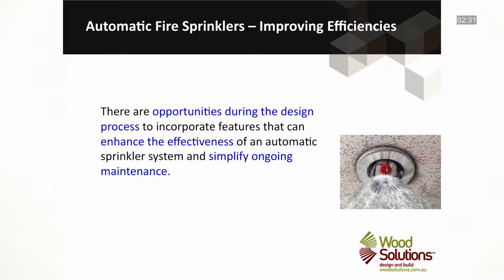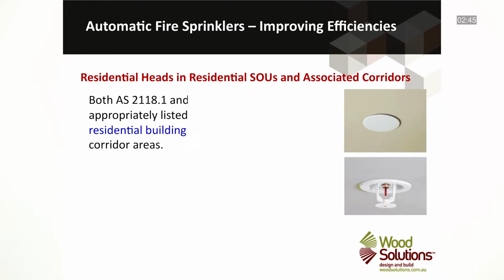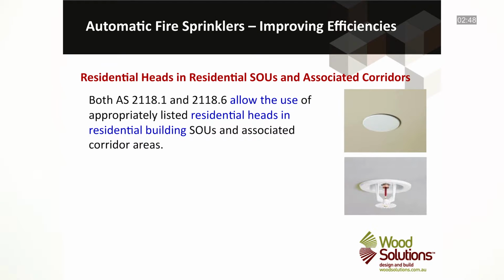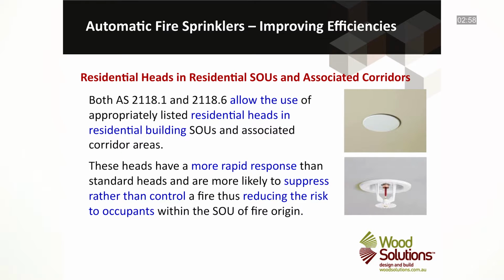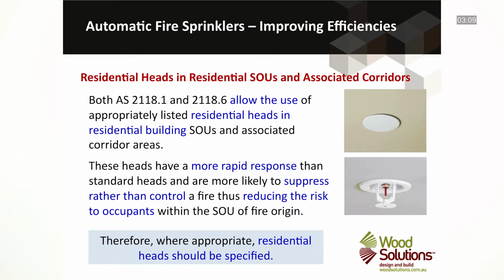There are also opportunities during the design process to incorporate features that can enhance the effectiveness of an automatic sprinkler system and simplify ongoing maintenance. Sometimes there is a related cost, but often the cost is quite minimal, whilst the benefits substantial. A few examples of effective approaches are as follows. Both AS2118.1 and 2118.6 allow the use of appropriately listed residential heads in residential building SOUs and associated corridor areas. These heads have a more rapid response than standard heads and are more likely to suppress rather than control a fire, thus reducing the risk to occupants within the sole occupancy unit of fire origin. It is recommended that where appropriate, residential heads should be specified, so talk to your services engineers. It makes sense to use them, as they enhance safety for little cost penalty.